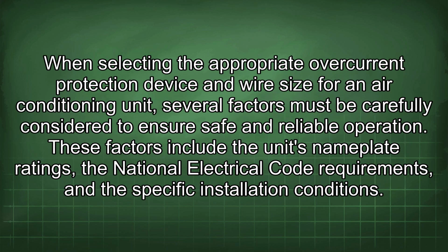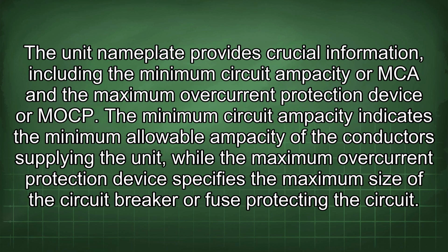When selecting the appropriate overcurrent protection device and wire size for an air conditioning unit, several factors must be carefully considered to ensure safe and reliable operation. These factors include the unit's nameplate ratings, the National Electrical Code requirements, and the specific installation conditions. The unit nameplate provides crucial information, including the minimum circuit ampacity, or MCA, and the maximum overcurrent protection device, or MOCP. The minimum circuit ampacity indicates the minimum allowable ampacity of the conductors supplying the unit, while the maximum overcurrent protection device specifies the maximum size of the circuit breaker or fuse protecting the circuit.